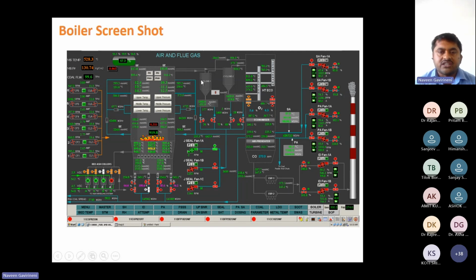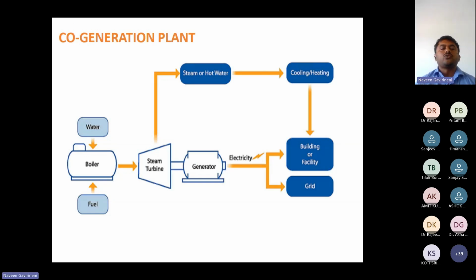While rotating, the particles fall down again into what is termed the cyclone loop seal. While supplying the fan, fluidization happens again. Here there is one fluidization, here there is another fluidization. After fluidization, it comes down to the furnace for maintaining the bed. After that it goes to the superheater, reheater, economizer, APH, finally ESP, and goes to the atmosphere through the ID fan. So this is the cogeneration plant.